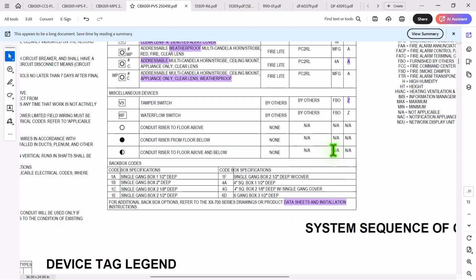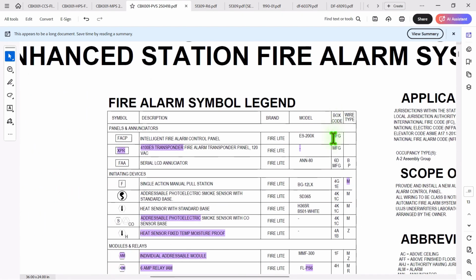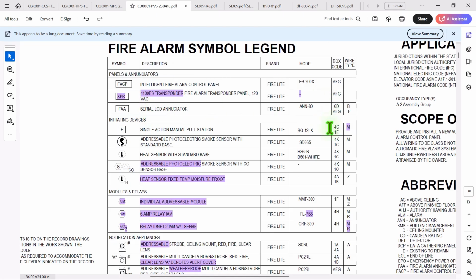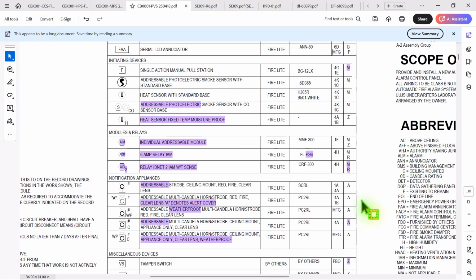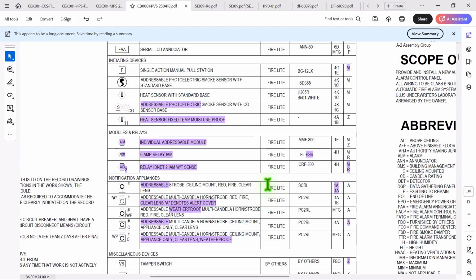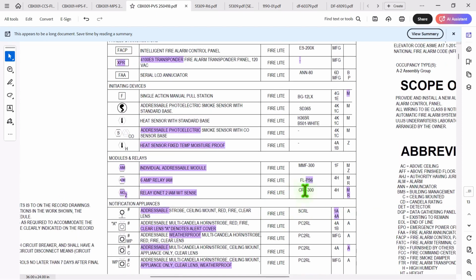When it comes to the box code, the remote annunciators - we could put a deep 1900 box for the remote annunciator. The horns and strobes are all going to be 1Fs, change this to 1F. All of these, the horns and strobes and even the strobes, are all going to just be 1Fs. The modules and the relays are going to be 4Gs.